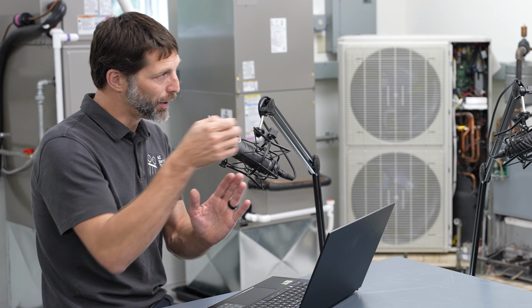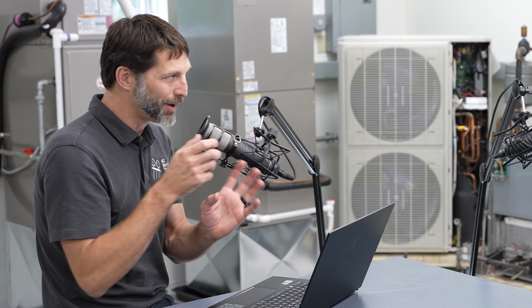Yeah. And one more thing, when you are testing electrical current, what I like to do is turn the power off to the system, kind of pull the wire out of a box. So when we're checking the current of something, what we can do is turn the power off and fish the wire out, get it accessed, and then put our clamp meter around it, because it has a magnet typically, and then go ahead and turn the power back on and let it go through its sequence. And then we can watch our current. We don't have to have our hands in there. You have to think about this safely.